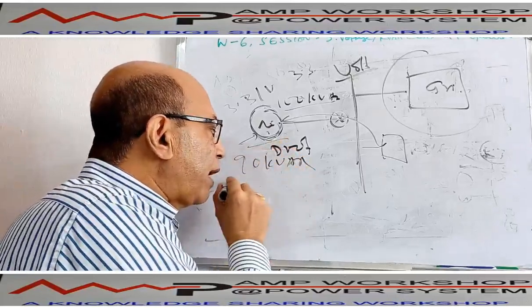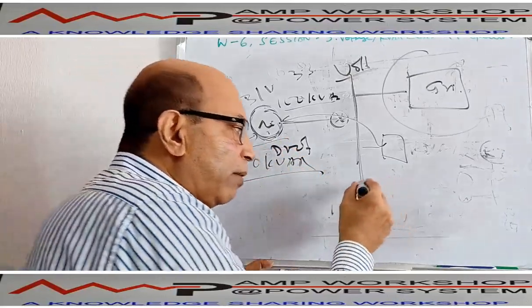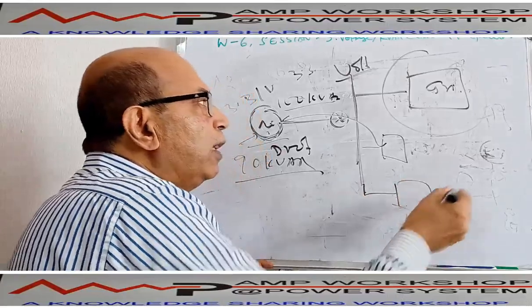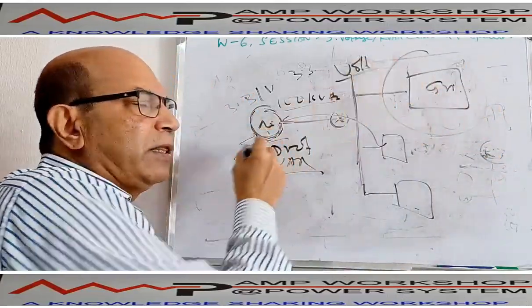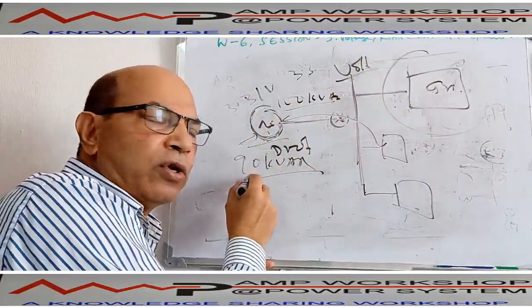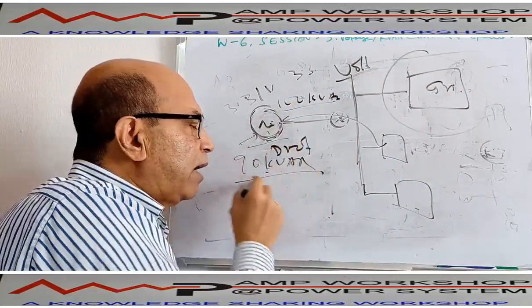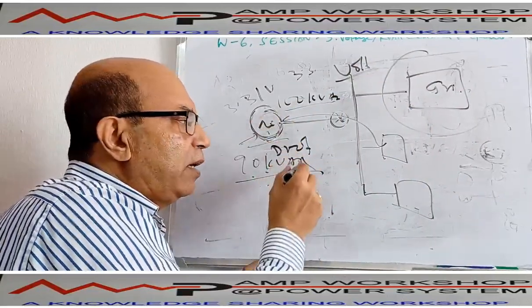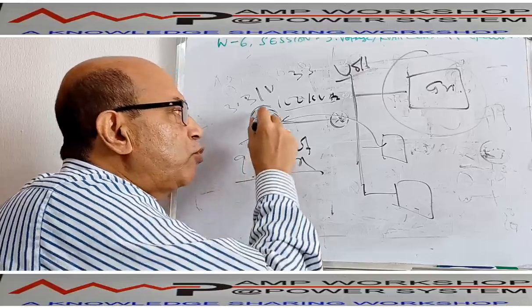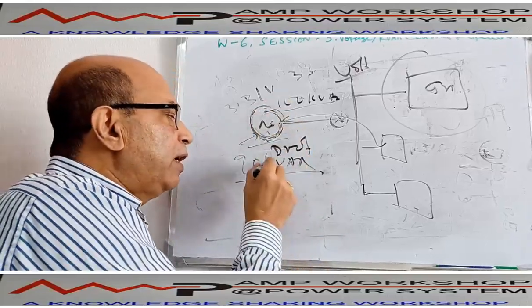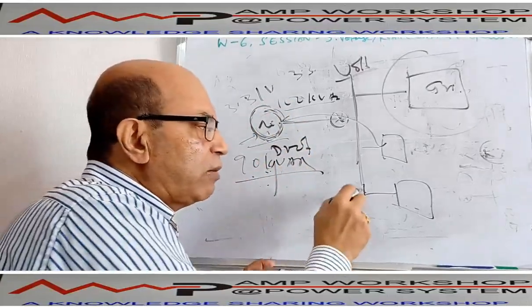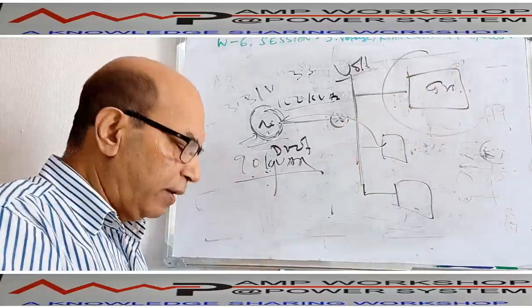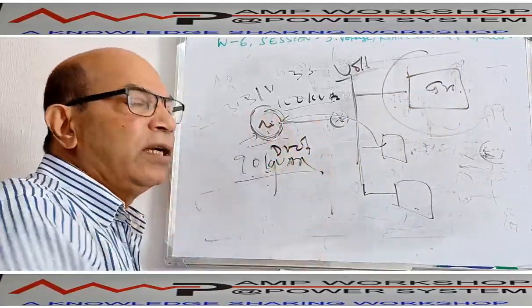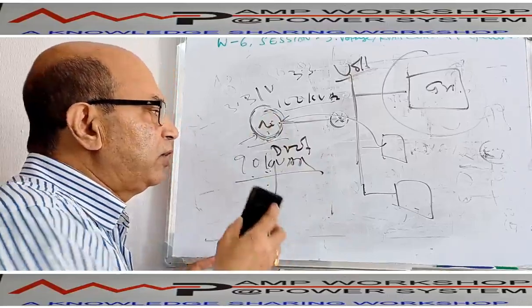Then this machine will be running with 90 kVAR, and whatever further load comes, all of it will be taken by the grid, not by this machine. Because this machine is running in droop mode, it cannot take any further load. If you want to put more load, you have to do it manually: you have to increase the excitation of the machine. Otherwise all the load will be taken by the grid. So this way we can use the droop control for the multi-machine system.